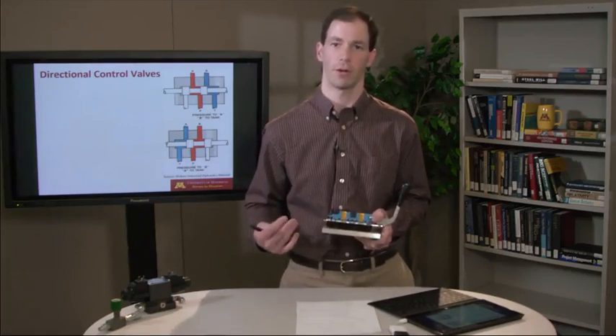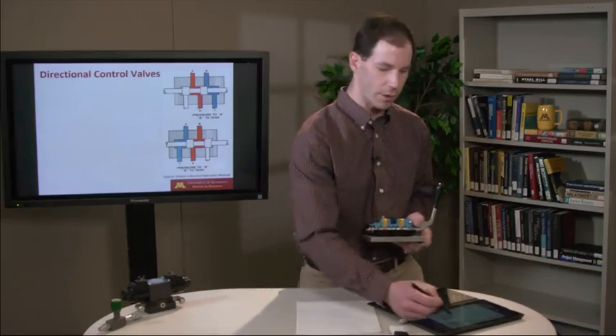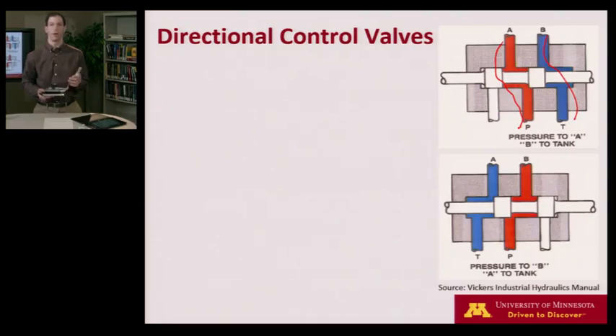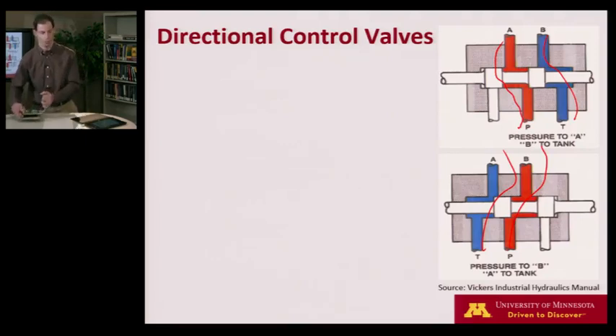In the top position I'm connecting my pressure to the A port and the tank to the B port, and that would cause the cylinder to move in one direction. As I shift the valve to another position, I connect the pressure to the B port and the tank to the A port. So just by moving the spool back and forth we can control the direction of the flow, hence a directional control valve.